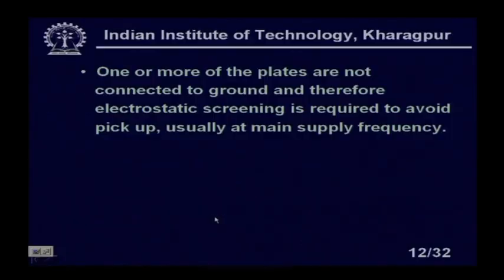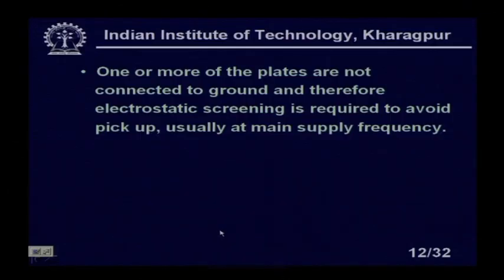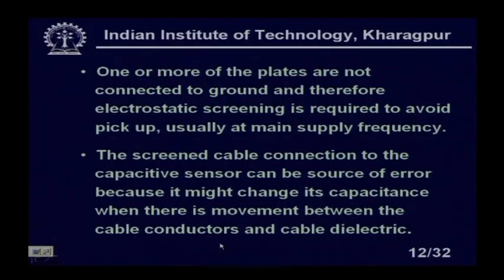One or more plates are not connected to ground, so electrostatic screening is required to avoid pickup. Capacitance values are very small and stray capacitance is always present, so signal processing circuitry must account for this. The 50 Hz mains supply frequency can be picked up, requiring proper shielding. The screened cable connection can also be a source of error if its capacitance changes when there is movement between cable conductors and cable dielectric.